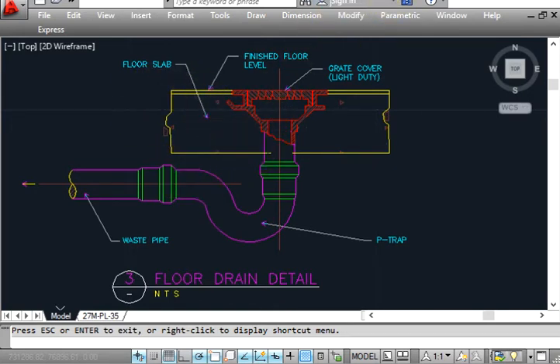This is the floor clean out detail. Floor clean out — basically whenever we reach the end of the pipe, we have to install a plug and provide a floor clean out. Floor clean out will have no P-trap because it will be closed all the time. Whenever there is a problem in the soil pipe — blockage or like that — we open the cap, push a wire, and put chemical from here so the water will drain and the pipe will be reopened. This is the purpose of a floor clean out. As per plumbing code, whenever the pipe reaches the end, we must provide a floor clean out.